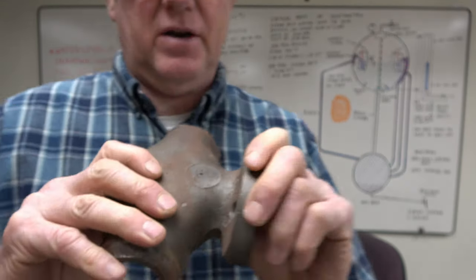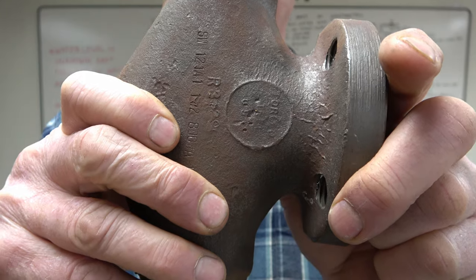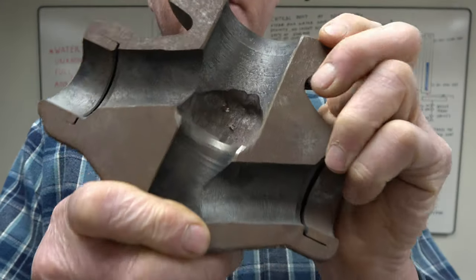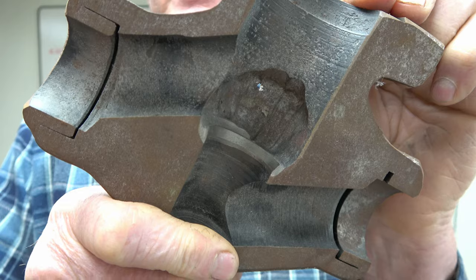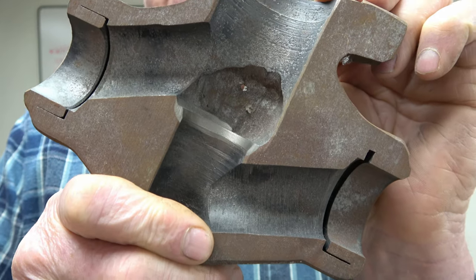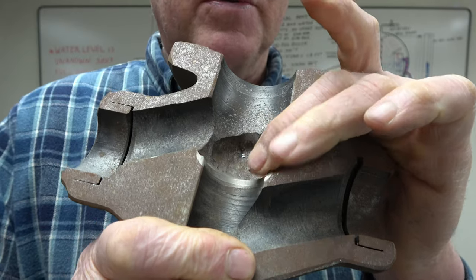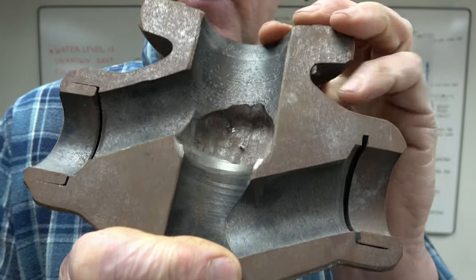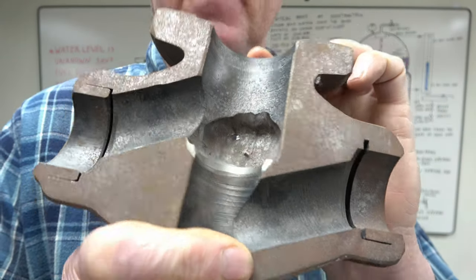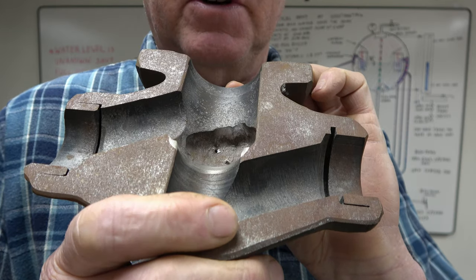Here's another valve that had started leaking out the side of it. As you can see it has substantial erosion damage on the upstream side of the seat. I don't know if the valve wasn't closed right, leaking through a little bit, but it cut through the valve body.